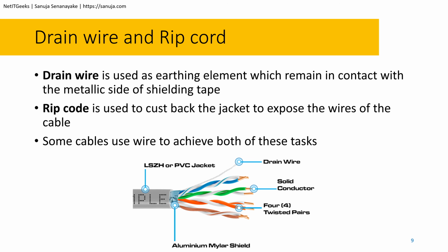A ripcord is used to cut back the jacket to expose the wires of the cable. This should say used to cut back, not cust back. Sorry about that. So sometimes the drain wire is also acting as a ripcord, allowing you to pull from this wire, and then it can rip through the outer shield, and that will allow you to expose the cable for installation purposes. So some cables use one wire to achieve both of these tasks, but some cables may have two wires associated with this. So if you don't have an aluminum shield or a metal shield here, this particular ripcord is most likely going to be some kind of nylon ripcord. But if you have aluminum shielding, this ripcord could be a drain wire and a ripcord in one. In that case, you will have this wire be metal.